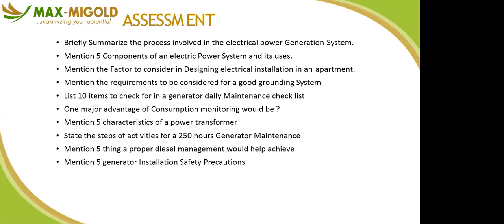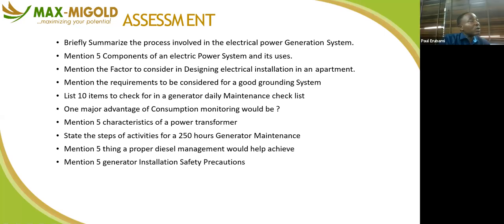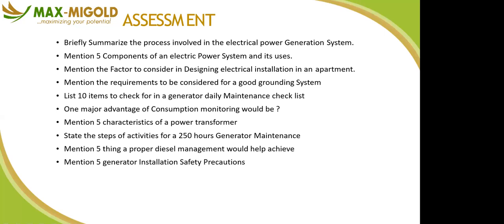Most companies are doing that. Where I work, we used to run 2,000 kVA by 3. But with time, we started reducing. Now we can run 1,000 kVA, 2,000 kVA to power the building. The same building they were using 2,000 kVA to run. So facility management is not static, it's progressive. As they come, you run, so that you do not run into trouble in terms of cost. Is that taken? Okay. Yes, sir. Thank you.